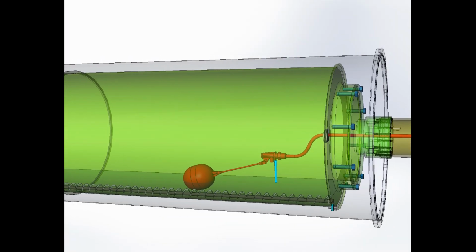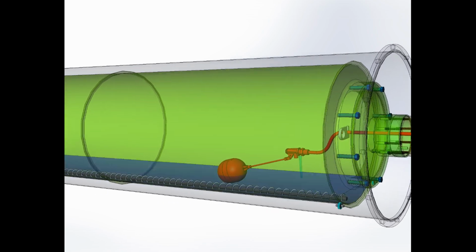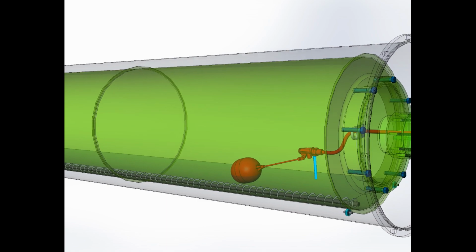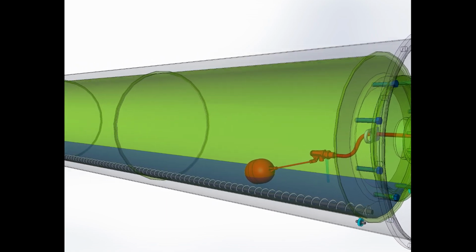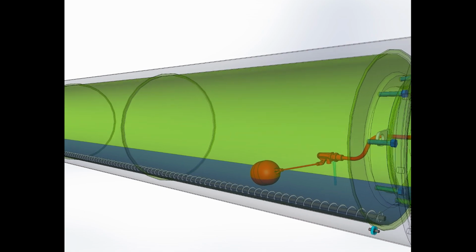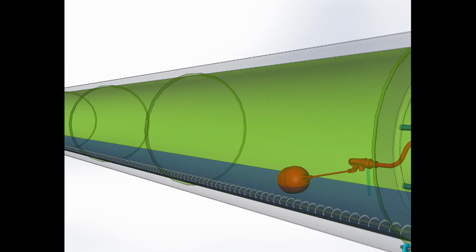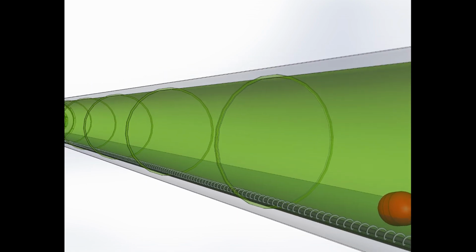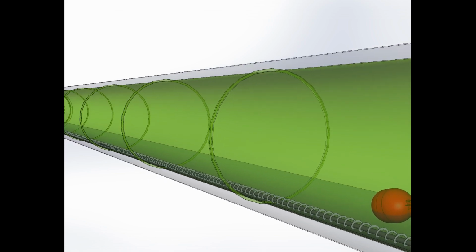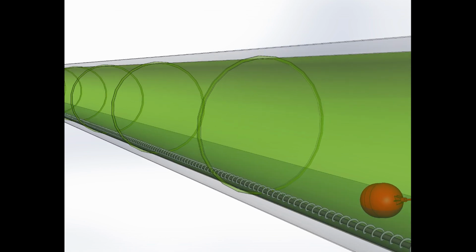The brine supply for evaporation and automatic maintenance of the specified brine level in the drum are carried out using a float valve. A spiral made of thin-walled tape with a heavy rod inside, rolling under its own weight below the brine level in the rotating drum, not only cleans the inner heating surface of the drum from salt deposits, but also transports the resulting sludge to the discharge point for concentrated brine removal from the drum.